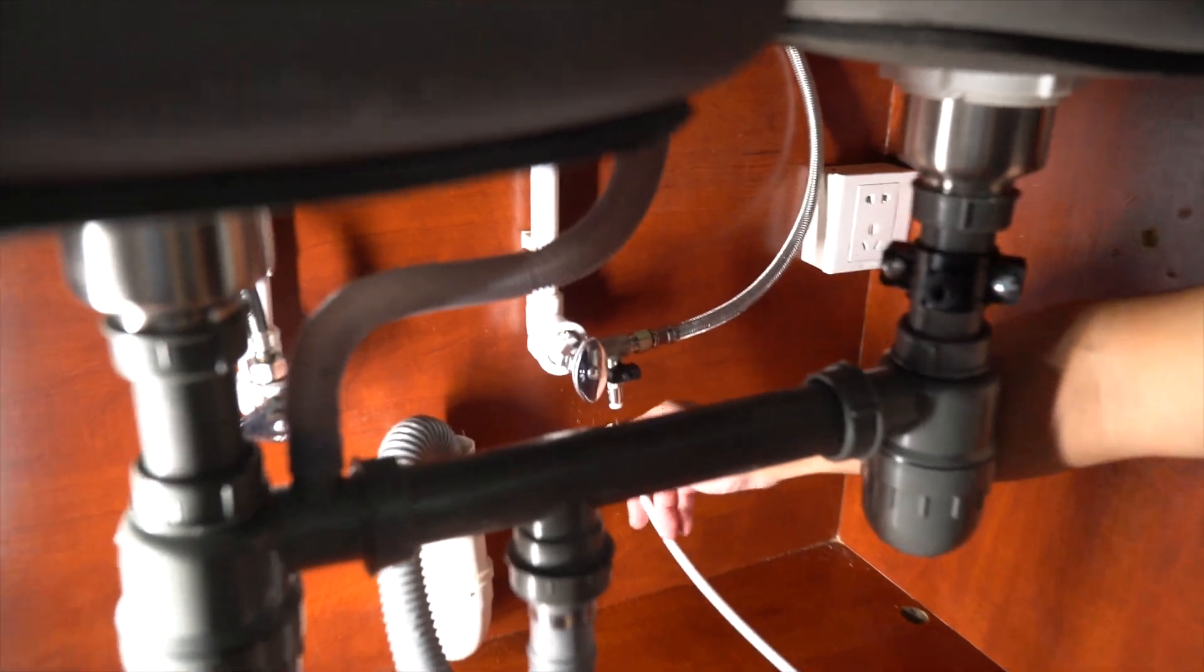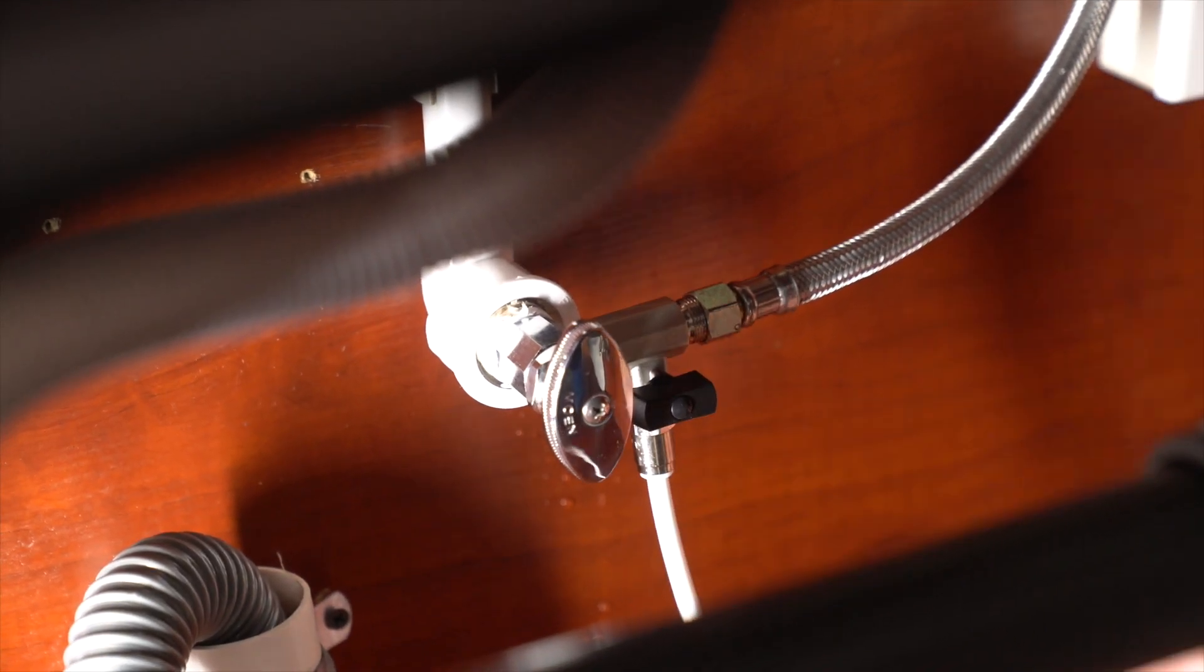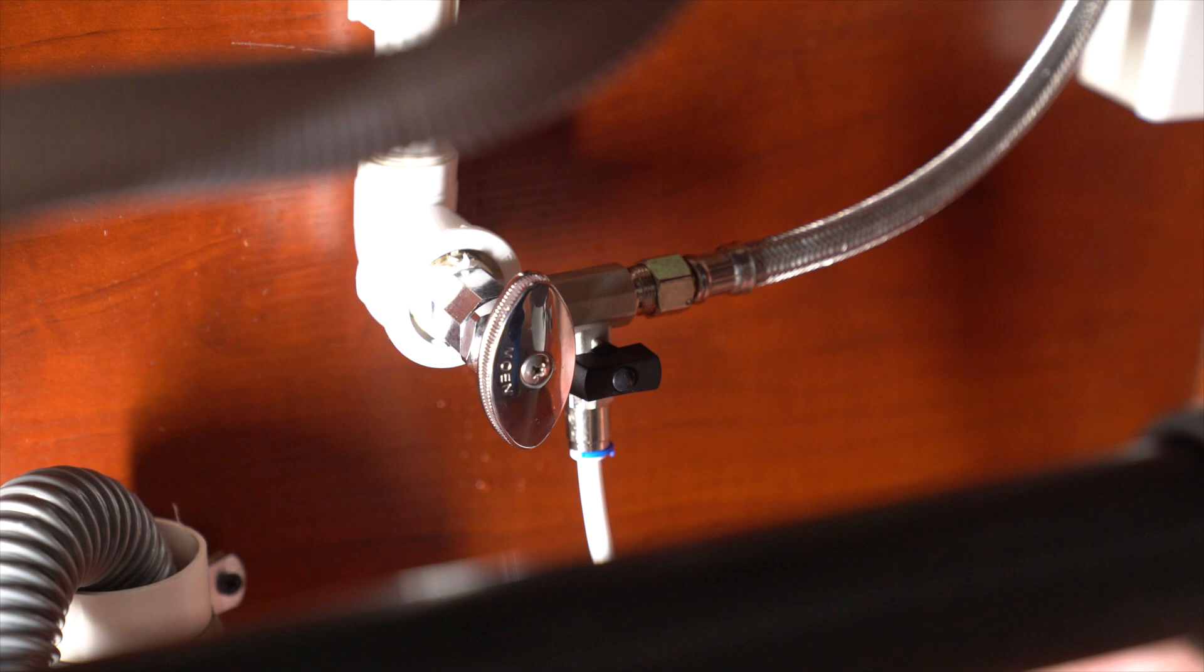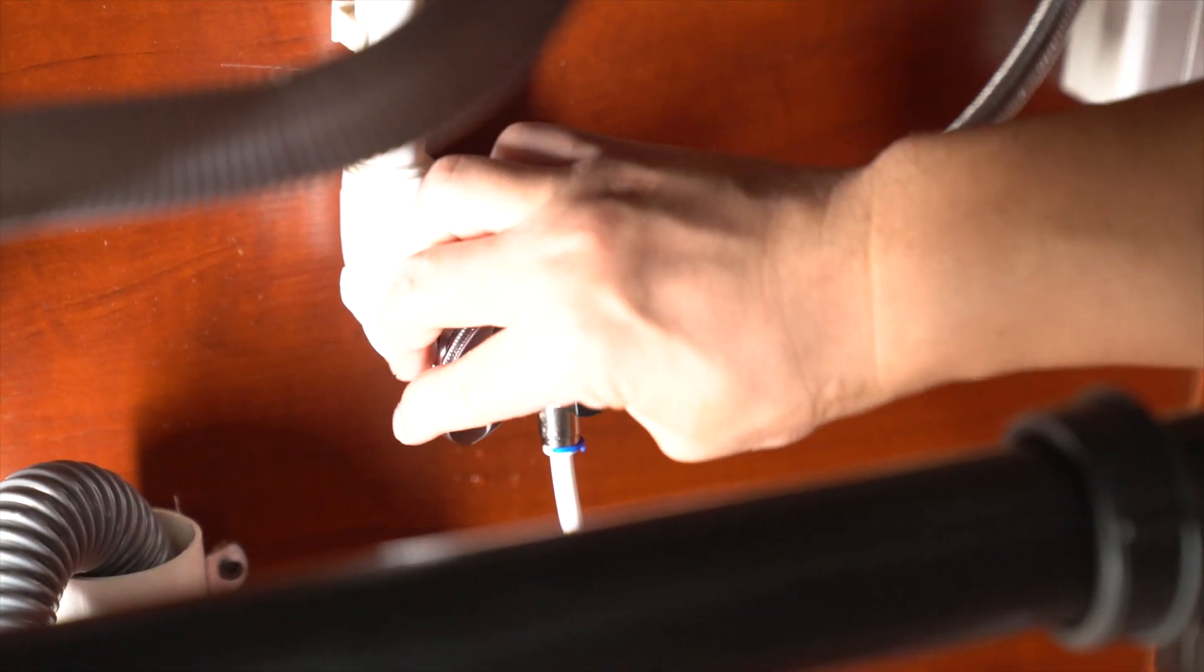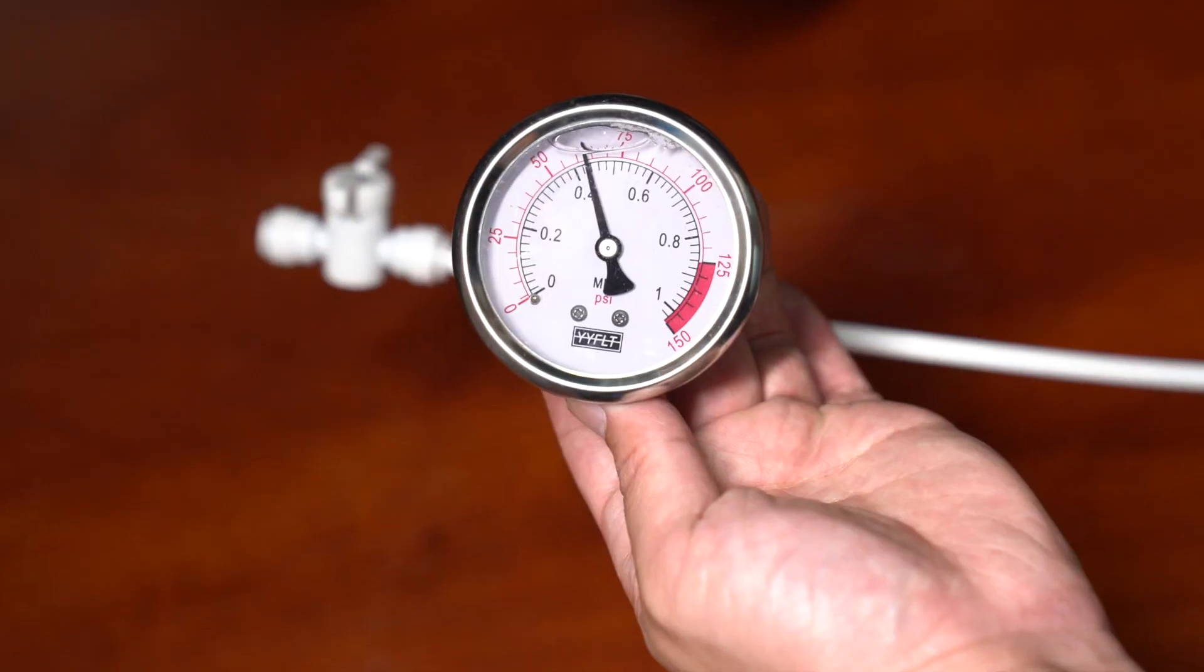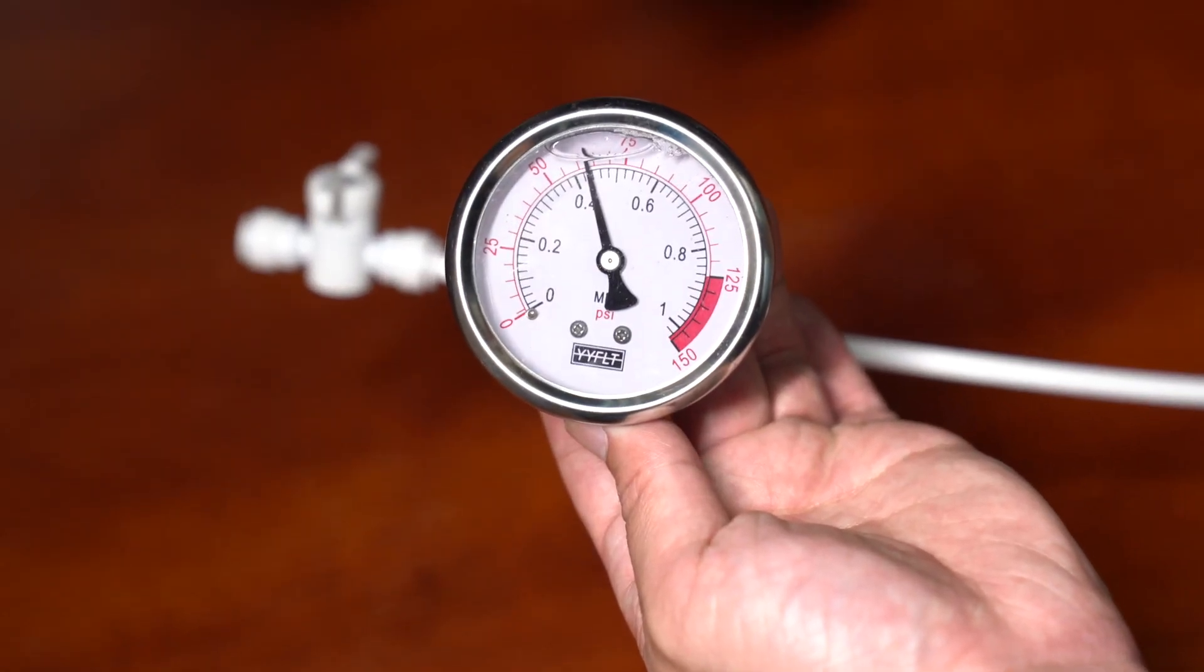Before you begin installation, confirm your cold water pressure is between 40 to 80 PSI using a pressure gauge. If lower than 40 PSI, a booster pump may be required. If over 80 PSI, a pressure reducing valve is required.